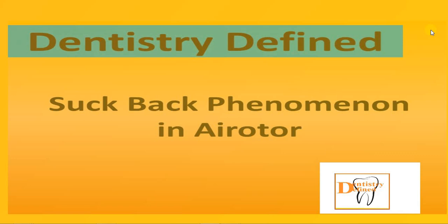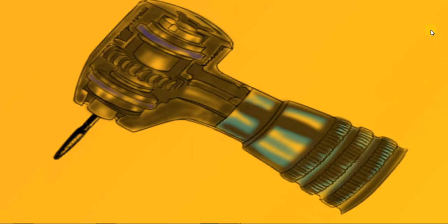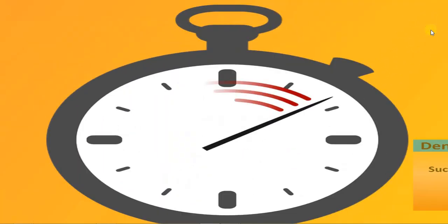The air rotor rotates by air with the help of an impeller inside the head of the handpiece. When we release the pedal, the air moving inside the air rotor is stopped — air is no longer supplied to the impeller. Still, it will continue to rotate inertially for a few seconds, then it stops rotating completely.